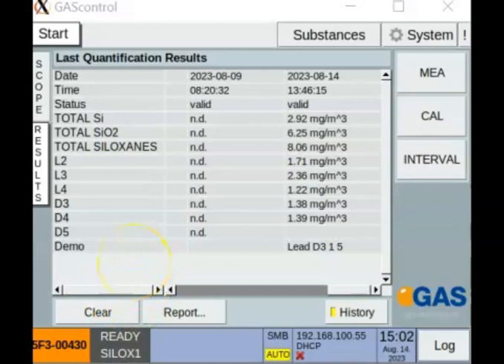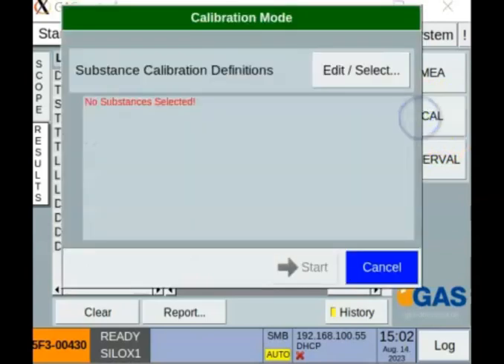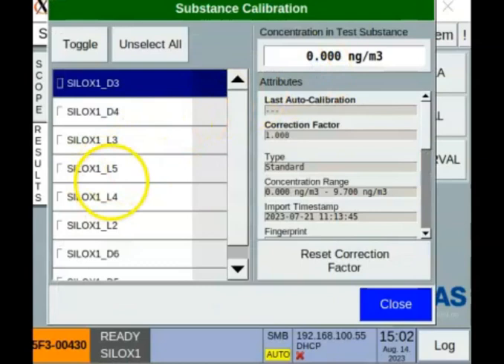The GC IMS SILOX can also be used to make a 1-point calibration. The idea is here that you need a test gas with a certified concentration, and you can provide a certain distinct concentration. Select the siloxane, which has to be recalibrated, enter the concentration and run this measurement. Once the measurement is successfully completed, it will apply a correction factor to the entire calibration curve.